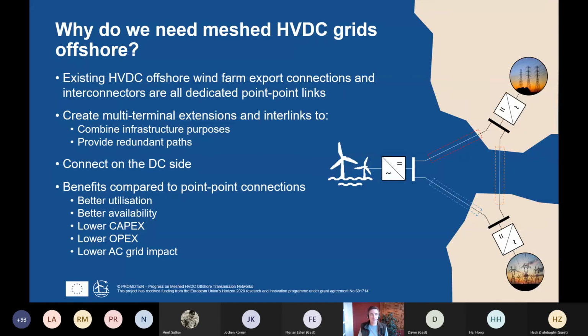And it has to do so quickly and selectively enough so that the operation in the healthy remainder of the network can be restored before the impact of the offshore DC fault on the onshore AC grids has become unacceptable. And to do so, HVDC circuit breakers and converters capable of interrupting DC fault currents are necessary to physically disconnect the faulty part of the network. And due to their high cost, this fault clearing equipment can only be placed at certain strategic locations in the network, balancing the protection selectivity with the impact of a DC fault on the onshore AC grid.